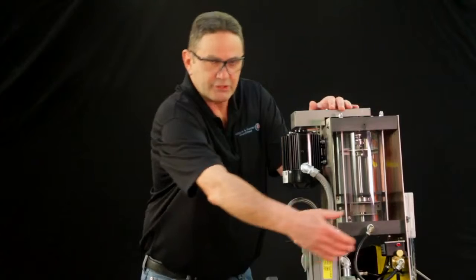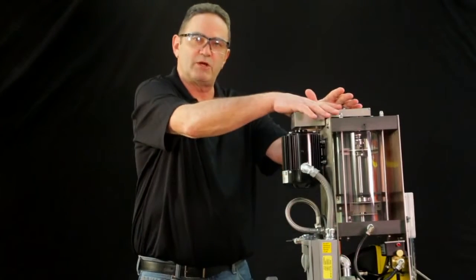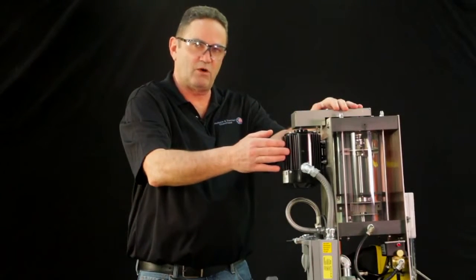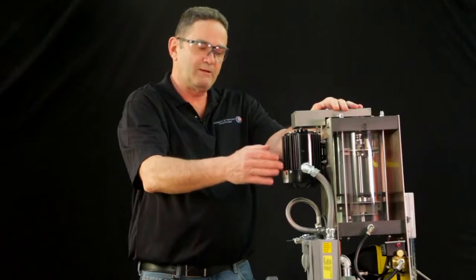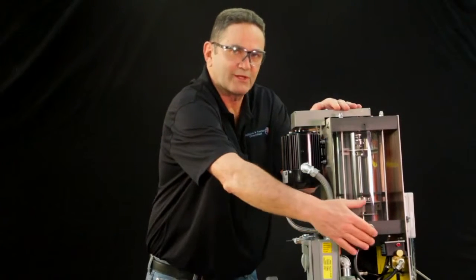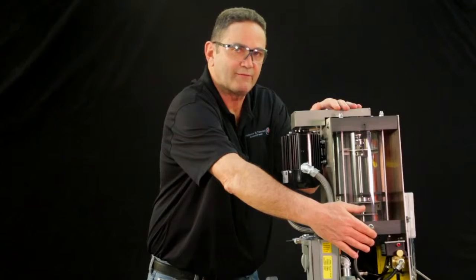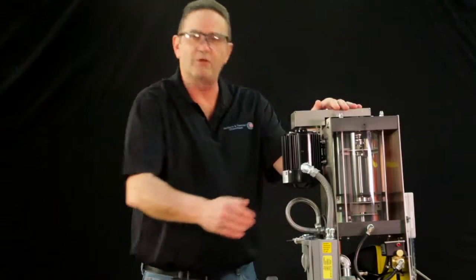Or if you have a deadhead situation, your differential will kick in, the mixer will be running, there actually will be no water flow, or it might be minimal water flow. But once you have the differential, the red light will light up indicating you have no flow. At no flow, the pump will not run.